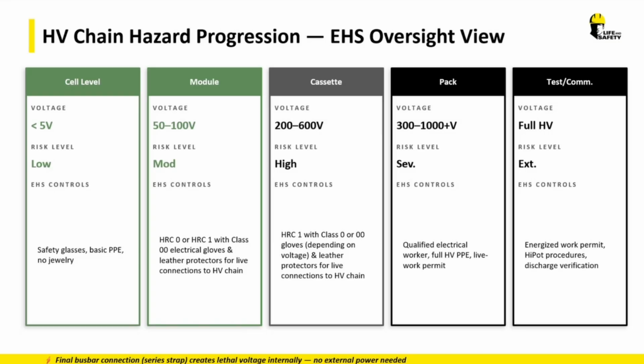You've got voltage and current. Voltage makes bad conductors better conductors, so as voltage goes up, you become a better conductor. Current only takes as little as 50 milliamps to stop the human heart, and everything from the module, cassette, pack, and up has more than enough current to kill you. That's where EH footwear and shock-protective gloves come in.